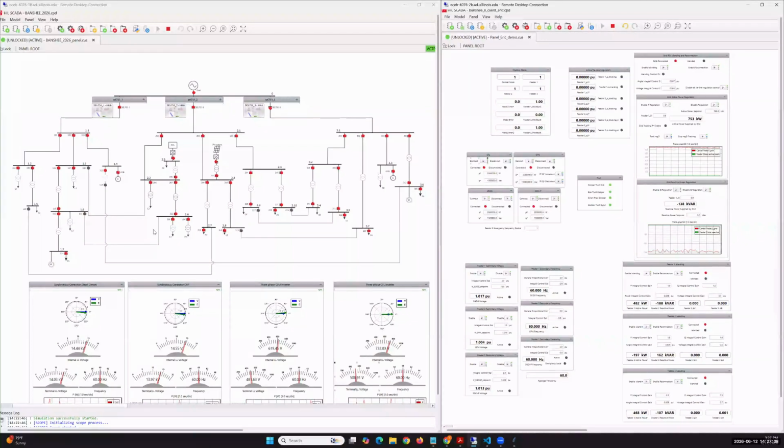However, for this test, we are going to introduce a malicious node on feeder 3. And the remedial action scheme for that will be to island this feeder from the grid and then turn on local frequency control on this microgrid. So by the end of the simulation, we should have one islanded microgrid over here and then one islanded microgrid over here that has been deemed malicious and distributed control has been turned off.